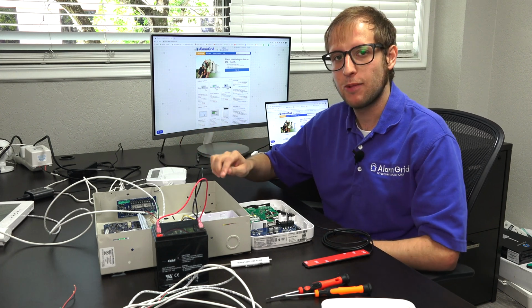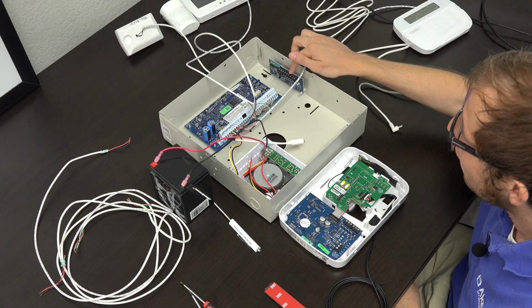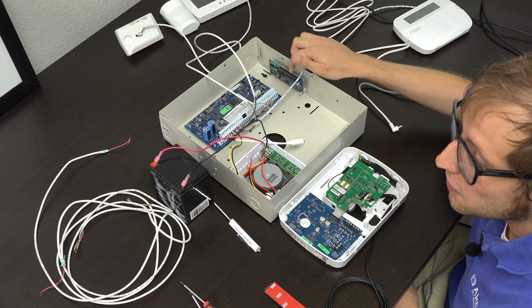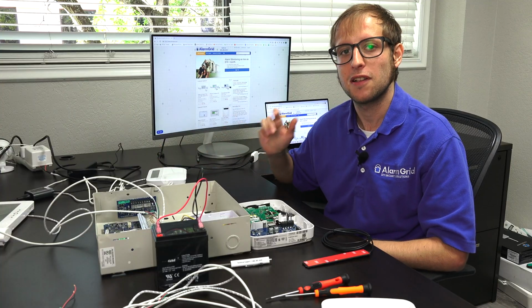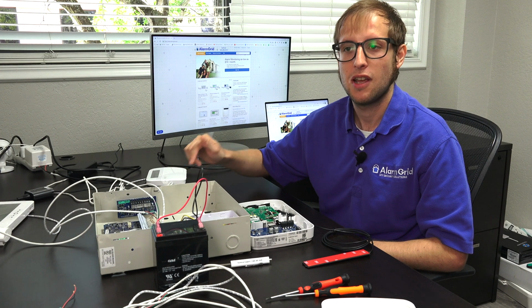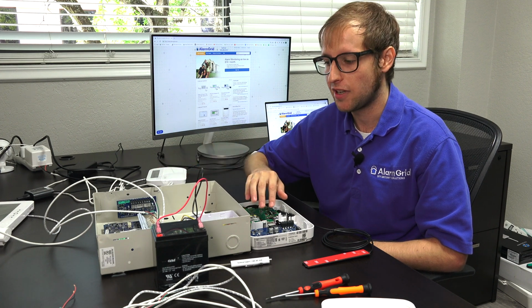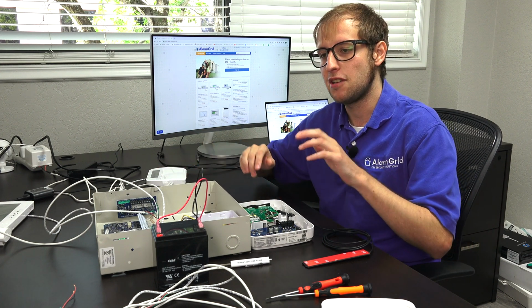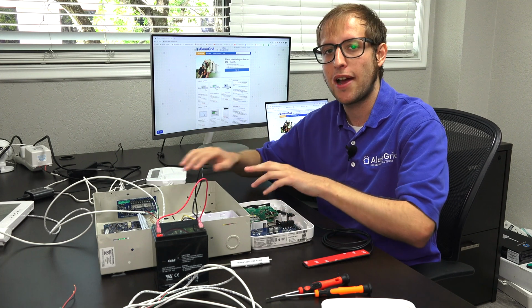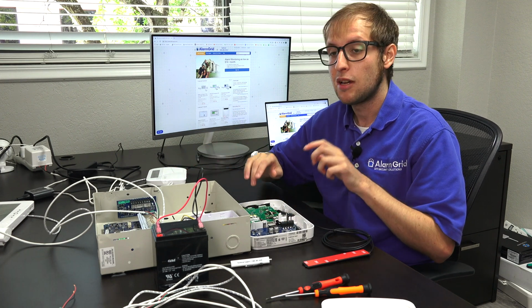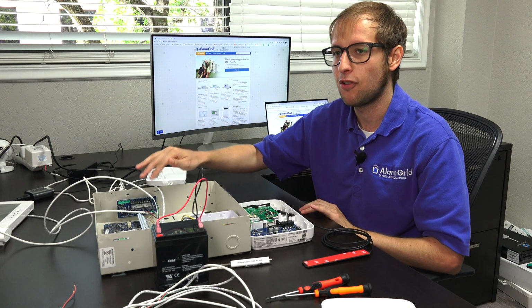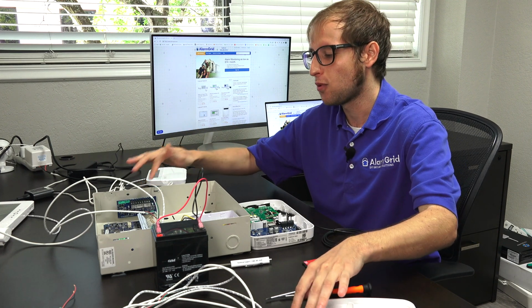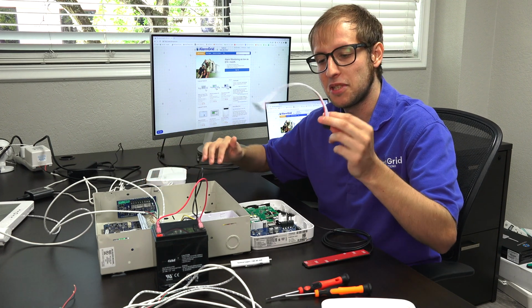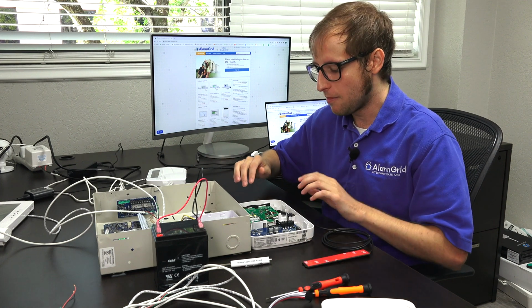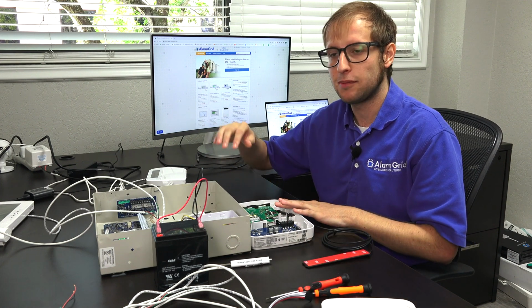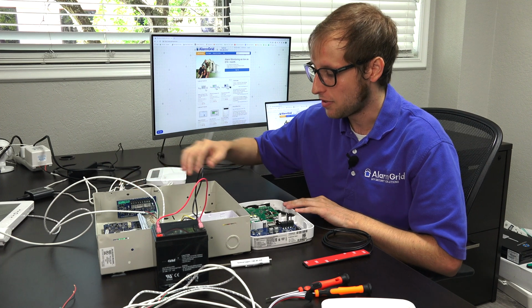Now, you will be working with the PCL422, which we have ours already mounted in the panel. This comes included with the communicator. We do sell it separately in case yours becomes lost or damaged, but you will need this to connect to the communicator. The way this is going to work, there's going to be a 4-wire connection and then another 2-wire connection, so 6 connections in total between the communicator and the PCL422. And then the PCL422 is going to use a link cable, which I'll be talking about in a little bit. But you're going to have 4 connections for data and 2 connections for power between the two.